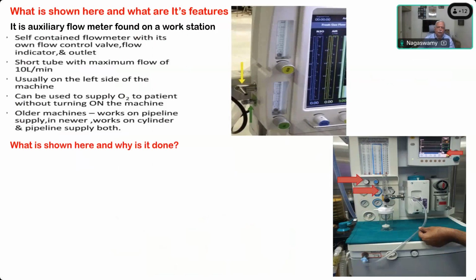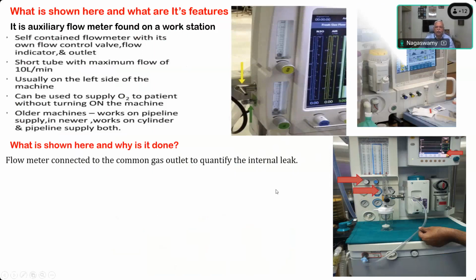So what does it mean? The oxygen knob is not on, yet there is oxygen leaking from the common gas outlet. A flow meter is connected to the common gas outlet to quantify the internal leak. Okay? So there is some leak occurring, so it is flowing through this, and you are able to see the flow there.